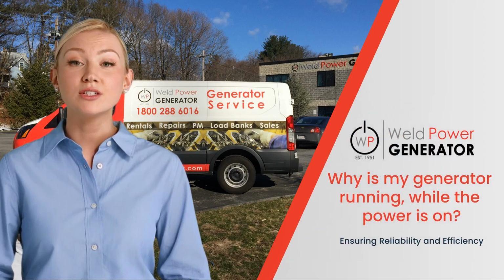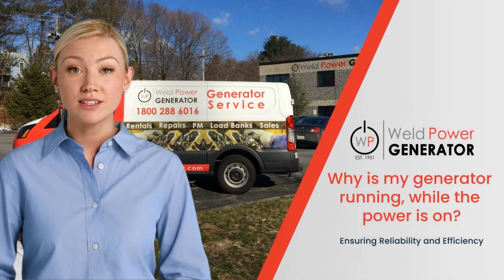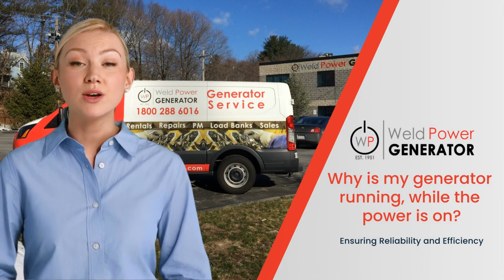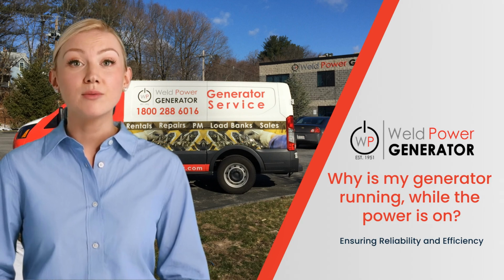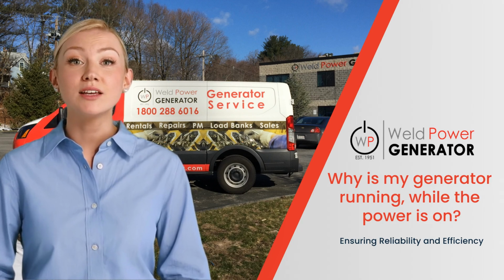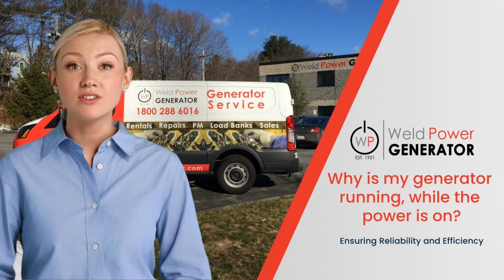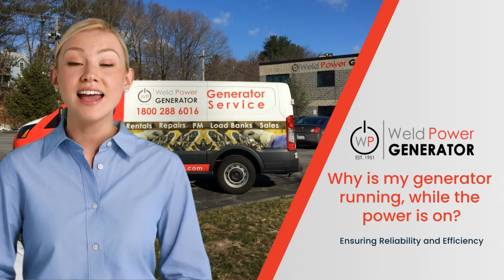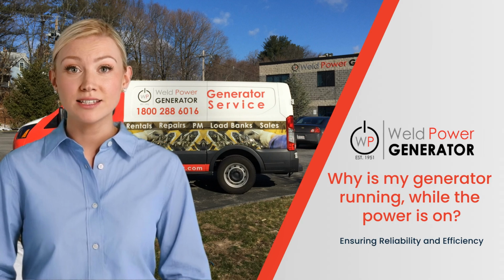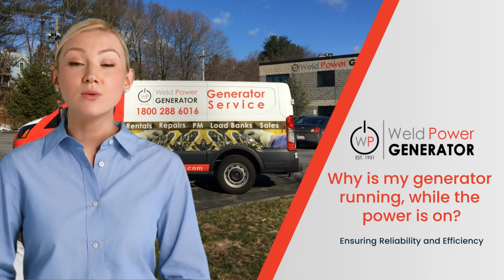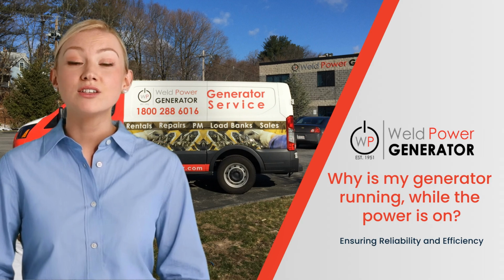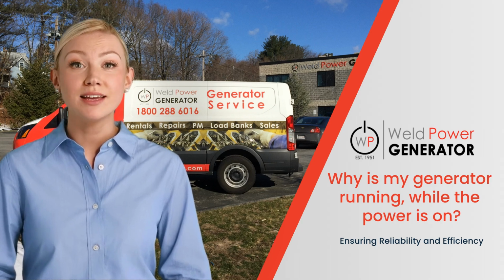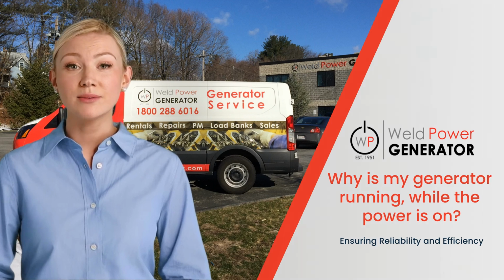For facility managers, building owners, and operators, seeing a generator running while utility power is available can be puzzling and concerning. A properly functioning generator should typically only operate when there is a loss of power, unless intentionally activated for testing or maintenance. If your generator is running while utility power is on, here are some common reasons why this might be happening and what you can do about it.